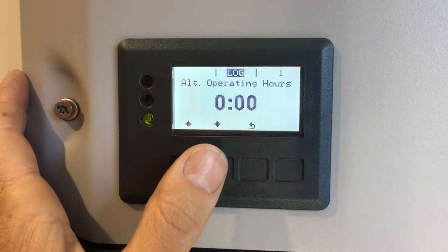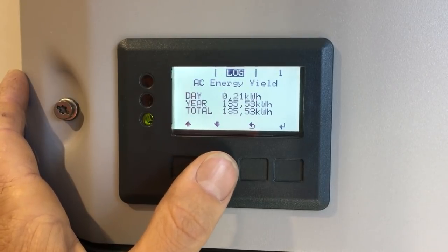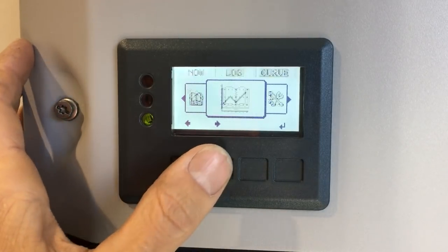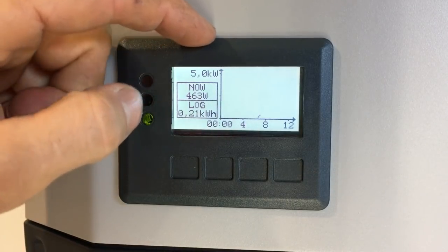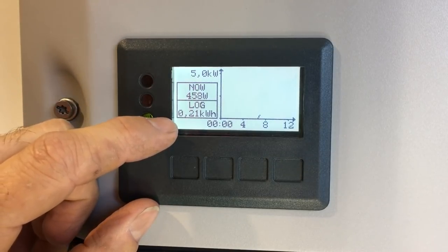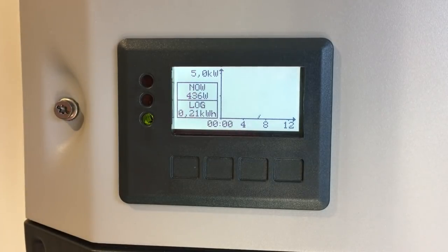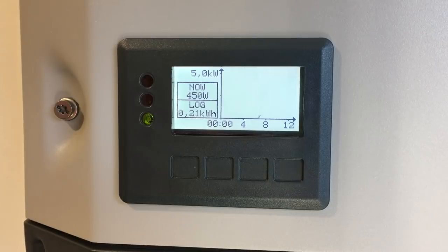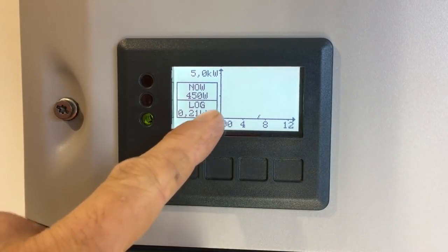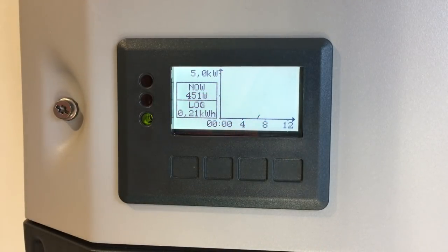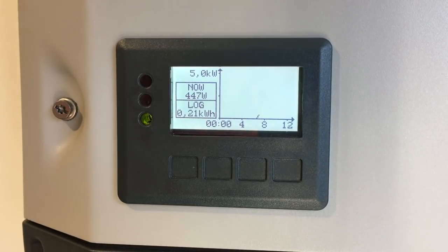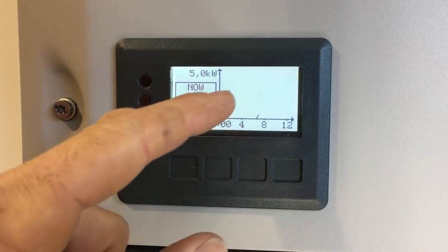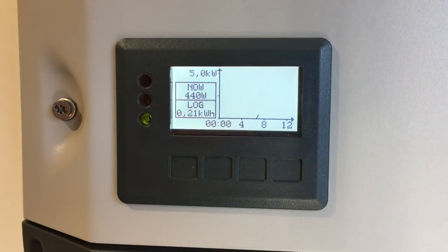After PV array maximum voltage, there are operating hours and alternate operating hours, then it cycles back to AC energy yield. Pressing back takes us to the Curve menu. This is a 5 kW inverter, so the top of the graph shows five kilowatts, displaying power produced right now and kilowatt hours produced today. Since it's early morning, there's only a tiny line showing solar has just started. On a sunny day the graph forms a nice bell curve; with intermittent cloud cover, you'll see jagged cuts in that bell curve where clouds pass over.